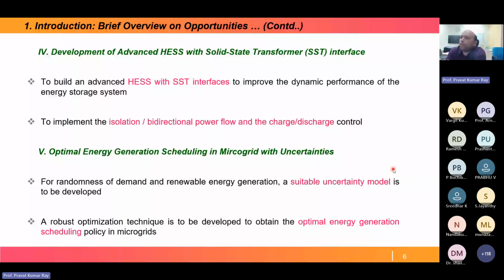Next, why is a solid state transformer interface required? Because a solid state transformer is nothing but a power electronic based transformer. When power electronics are involved, there is more flexibility in control—we can generate switching signals as per our algorithm or control, giving more flexibility in charge and discharge. So to implement isolation, bidirectional power flow, and more flexibility in charge and discharge control, we have to go for a solid state transformer. This way we can improve the efficiency or performance of a microgrid.